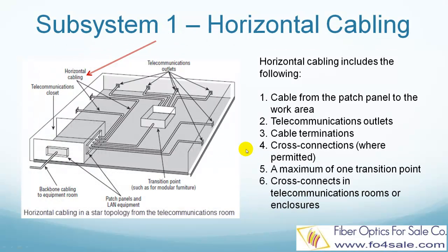Horizontal Cabling is the cabling that extends from the horizontal cross-connect, or main cross-connect, to the work area and terminates in telecommunications outlets. It includes cable from the patch panel to the work area, telecommunications outlets, cable terminations, cross-connections, and cross-connects in telecommunication rooms or enclosures. This figure shows a typical horizontal cabling infrastructure in a star topology from a telecommunications room, typically connected into patch panels and switches or hubs.